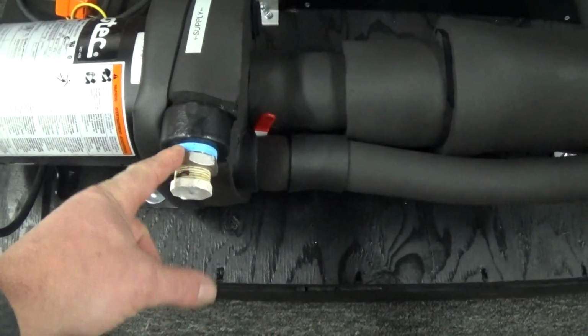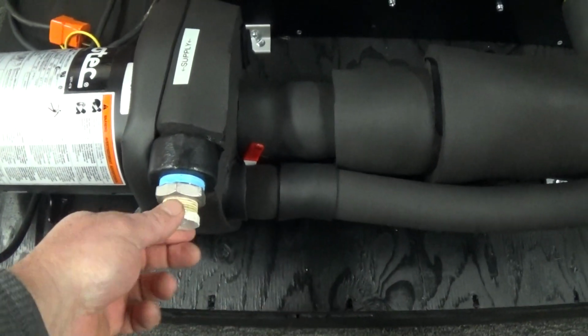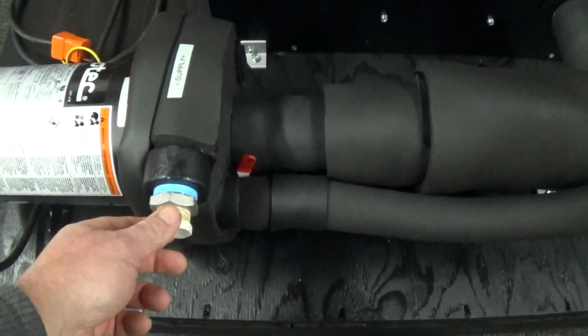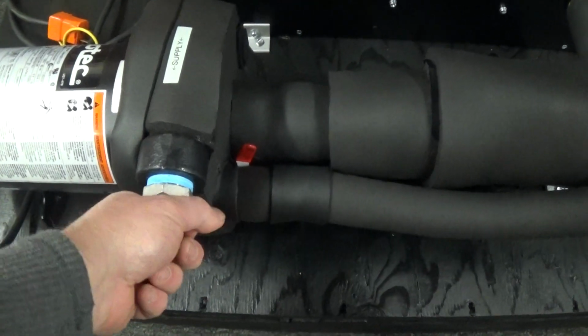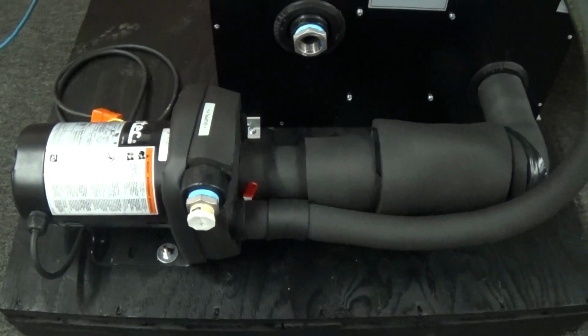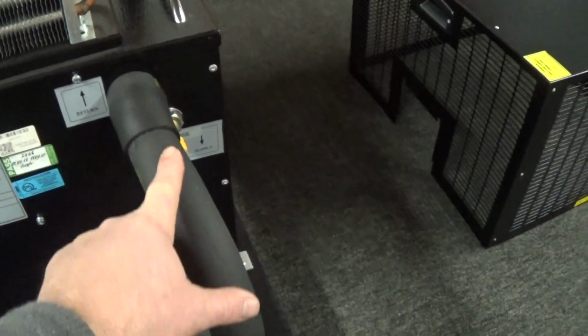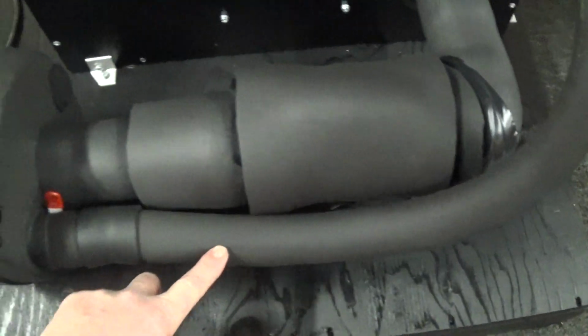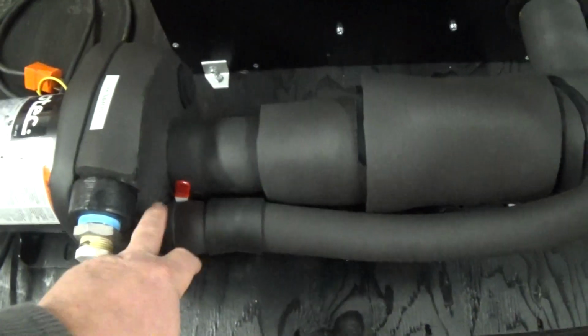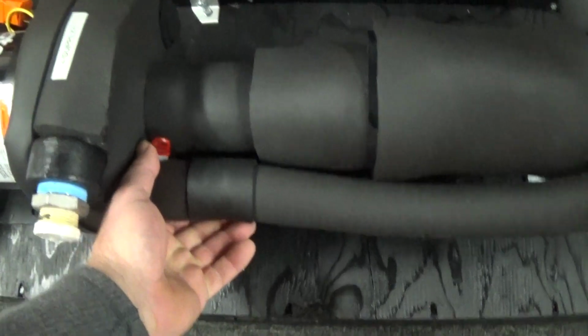This is a step-down bushing here. That remains there. This is just a 3/4 inch plug. Take that out. You're going to have 3/4 inch piping going to the supply line for your Glycol loop. This here is a bypass line we put in, approximately 3/8 of an inch, which draws off the impeller housing.